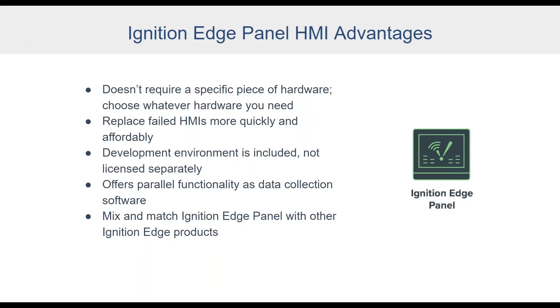Second, you can replace failed HMIs more quickly and affordably. If your HMI is an isolated all-in-one unit and it fails, you'd have to replace it with the same all-in-one unit and restore the project that was on it. But if it's decoupled and the HMI fails, you can just install it on a new panel PC of any brand, install the same software, and you're back in business — much simpler and more economical.